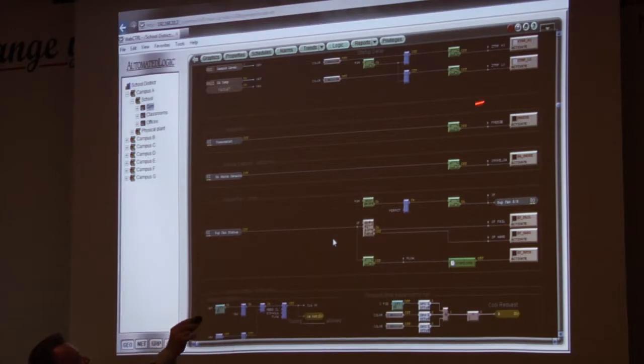So this one is all about the freeze stat. So freeze stat logic's in here. Smoke detectors in here. Supply fan control. This is what I'm looking for. I could see it says command on. All right, but see my status says off. So what do you guys think I'm going to do?